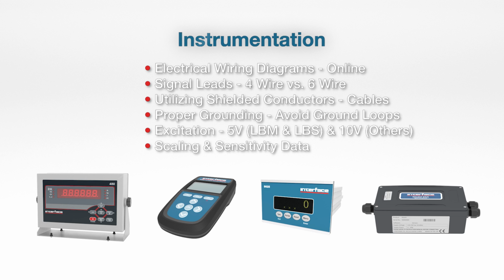Signal leads: we have 4-wire and 6-wire configurations on these load cells. 6-wire is going to offer something called sense. Some instrumentation may support that. If you order a cable from Interface for a standard low profile load cell, our standard 6-wire cable will support that sense function. For other applications, most times you can get away with just pairing that with excitation. Obviously, we would recommend using the proper cabling, shielded conductors, and avoiding ground loops in any wiring.